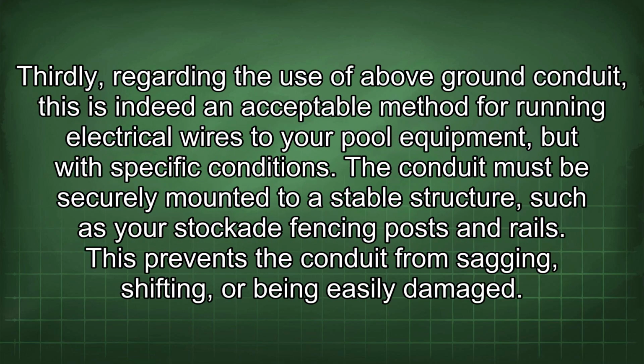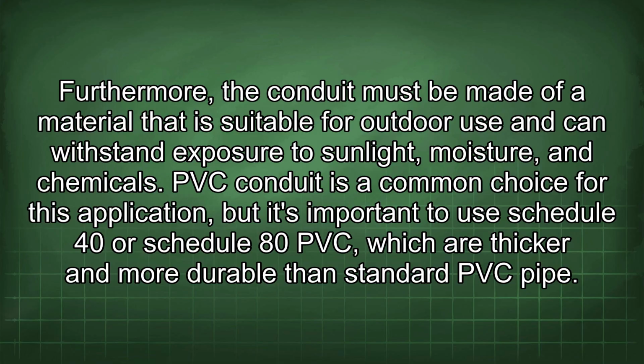Thirdly, regarding the use of above-ground conduit, this is indeed an acceptable method for running electrical wires to your pool equipment, but with specific conditions. The conduit must be securely mounted to a stable structure, such as your stockade fencing posts and rails. This prevents the conduit from sagging, shifting, or being easily damaged. Furthermore, the conduit must be made of a material that is suitable for outdoor use and can withstand exposure to sunlight, moisture, and chemicals. PVC conduit is a common choice for this application, but it's important to use Schedule 40 or Schedule 80 PVC, which are thicker and more durable than standard PVC pipe.